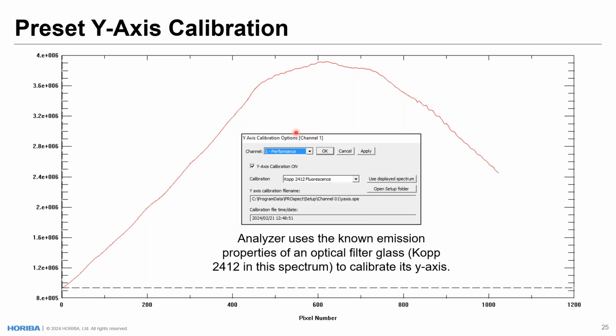So all in all, really, the laser wavelength, the x-axis, and the y-axis calibrations essentially zero out any laser wavelength drifts, the analyzer's fiber optic systems, and the collection probes. And so these all positively affect the transferability of the models from a laboratory analyzer, for example, to your online analyzer.